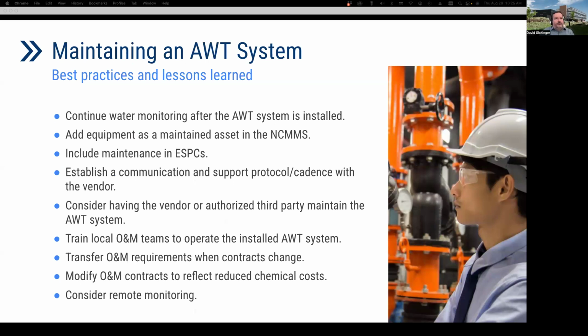So then, continuing the best practices in terms of maintaining an AWT system, really suggest that you continue water monitoring after it's installed, by a water treatment company, the AWT vendor or staff with specialized training. This all helps to provide early detection of potential issues and whether set points or operations need to be adjusted. Things can change from cooling season to cooling season as perhaps the load changes. So again, having trained staff is key. Mentioned before, but we're stating again, just because this has cropped up in some of the evaluations, make sure to add equipment in a national computerized maintenance management system.